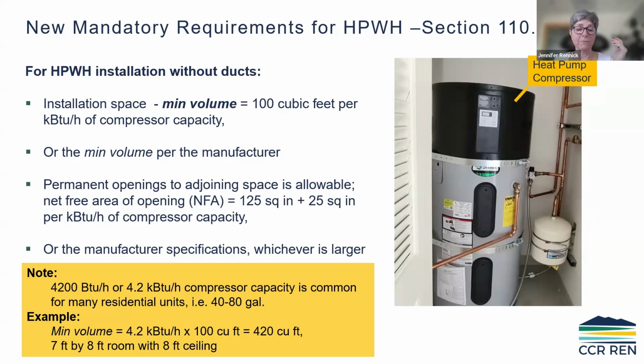And what that translates into is, for one of these heat pumps, you might need a room that's 7 feet by 8 feet with an 8-foot ceiling. If you don't quite have that, but you have a pretty generous closet, you can then calculate a net free area for a fully louvered door and have it communicate with the larger space. Then overall, you would meet that code requirement for the volume of space needed.